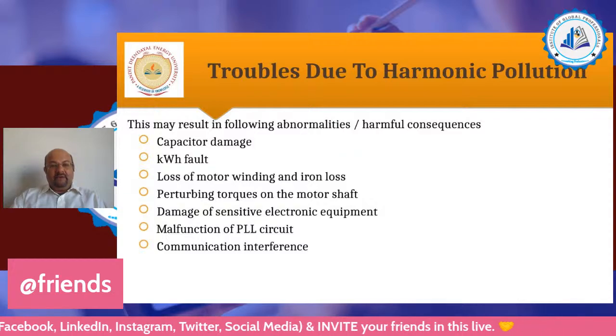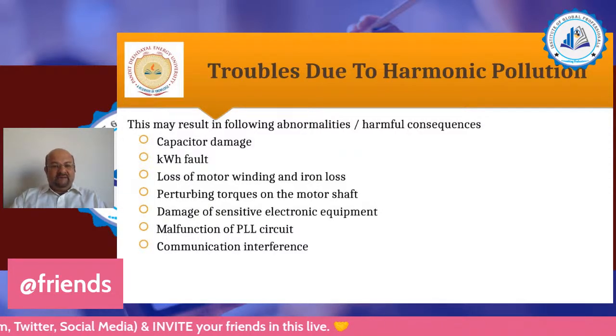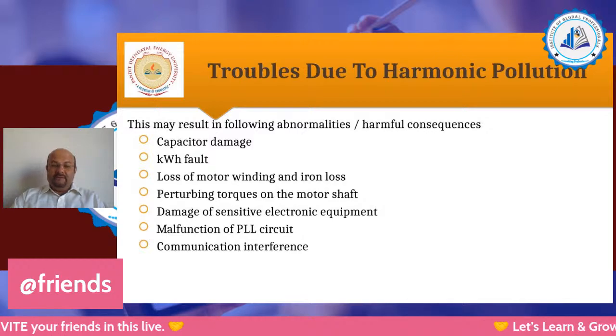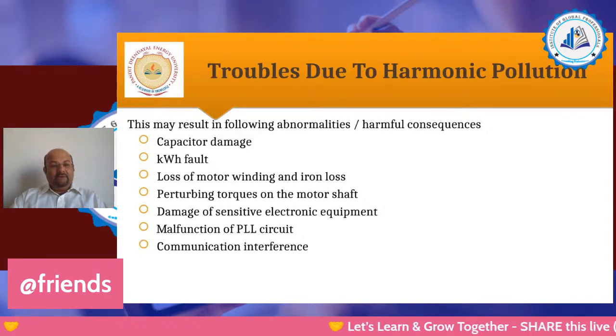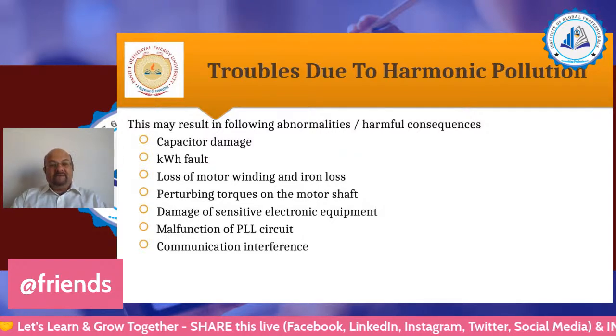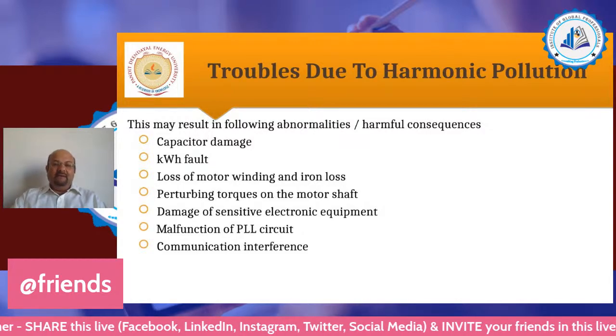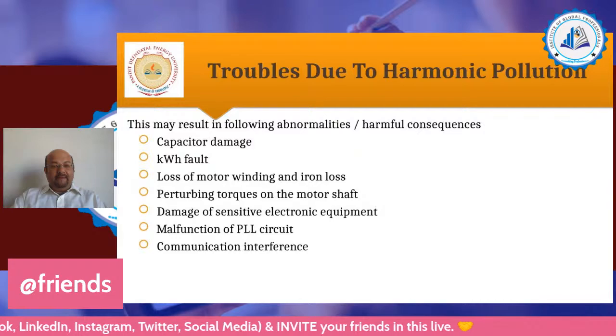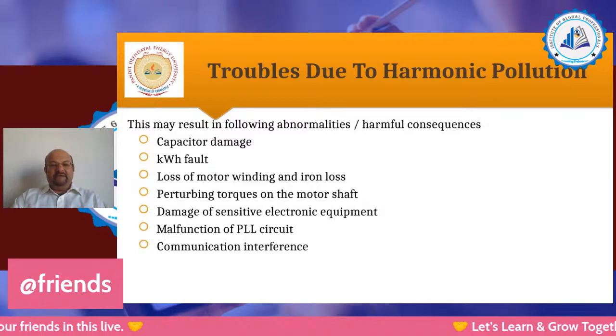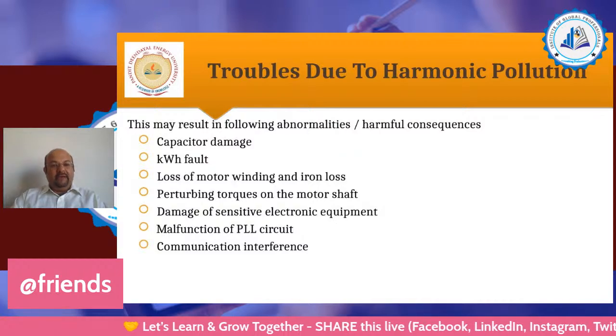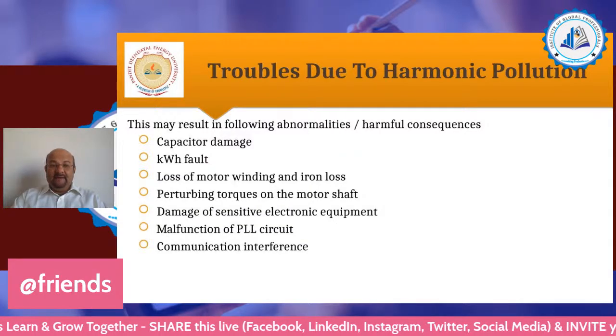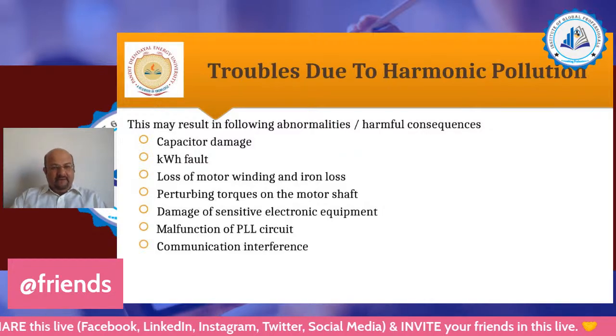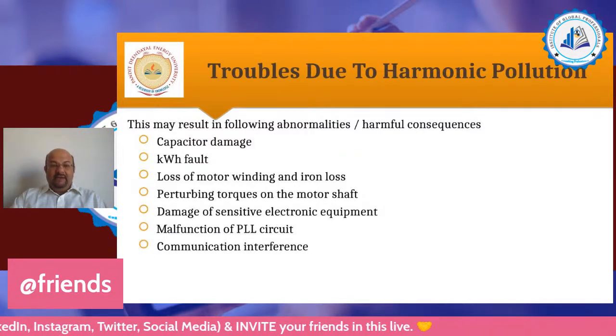Damage of sensitive electronic equipment, that we have already seen. Malfunctioning of phase locked loop circuit, that we also considered: whenever there are multiple zero crossings, the fundamental zero crossing is missed, or the electronic circuit is confused as to which one is the original fundamental zero crossing for measurement. So the PLL circuit will definitely malfunction. Again, if the frequency of this interference is very high, then it will be induced into the adjacent communication links, which are carrying very sensitive and important data for control or measurement, and that causes a big problem.